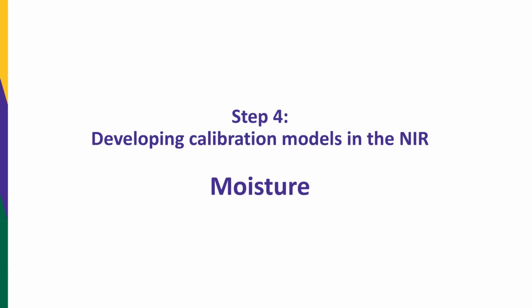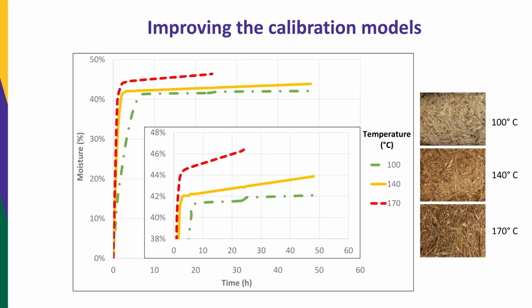Now, for moisture. From last year, I showed you some calibrations, and this is one of those. The calibration was not good at all. The R square is only 60%. And I was thinking, what can I do to improve this methodology, to improve the calibration? So I went back again to the methodology to measure moisture. Because remember, if we calibrate the equipment using a methodology that is not accurate, my calibration is not going to be accurate either. So I need to be sure the methodology I'm using is accurate enough.